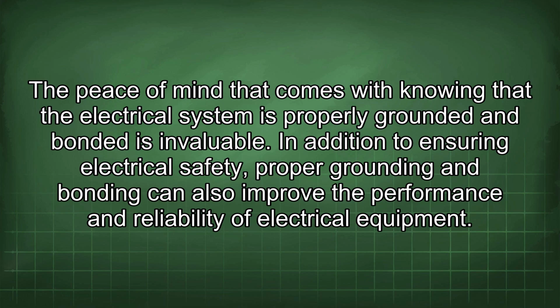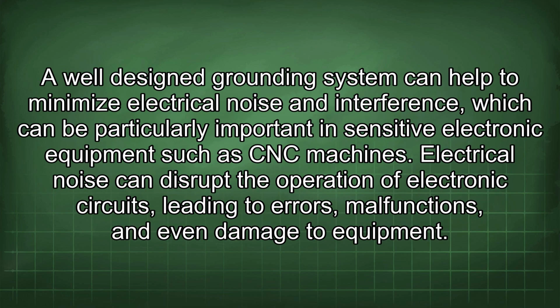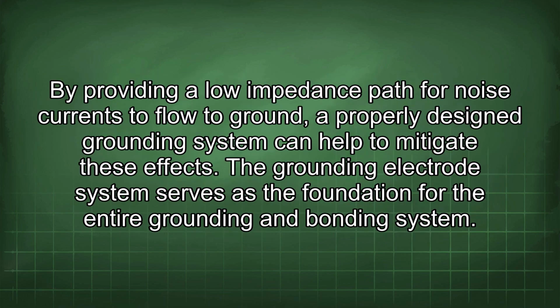In addition to ensuring electrical safety, proper grounding and bonding can also improve the performance and reliability of electrical equipment. A well-designed grounding system can help to minimize electrical noise and interference, which can be particularly important in sensitive electronic equipment such as CNC machines. Electrical noise can disrupt the operation of electronic circuits, leading to errors, malfunctions, and even damage to equipment. By providing a low impedance path for noise currents to flow to ground, a properly designed grounding system can help to mitigate these effects.